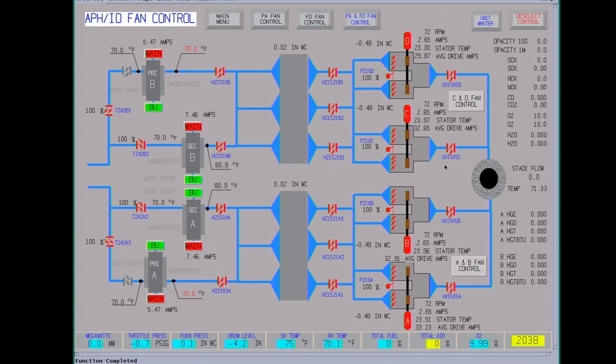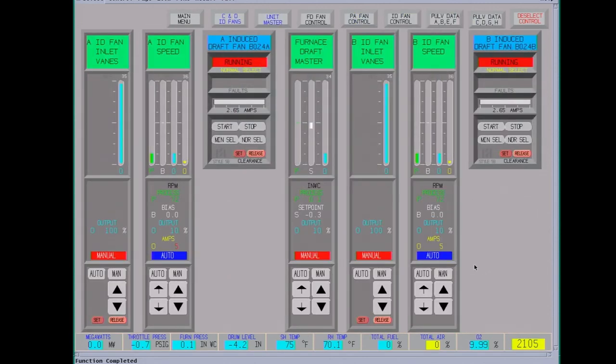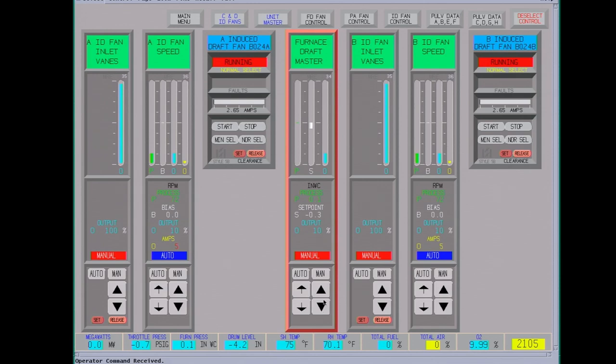Stack's about 650 feet tall, so it does provide some natural draft. When the plant's shut down you leave all the dampers open, it pulls a pretty good wind flow through the boiler, the wind boxes, people doing work in there. So there's normally a good draft through this. Okay, our ID fans are all in normal select, which means they're good to run. Furnace draft's in manual.